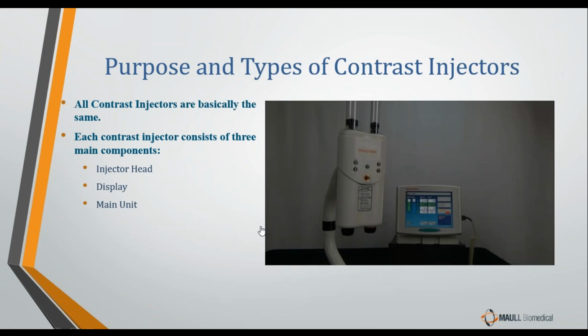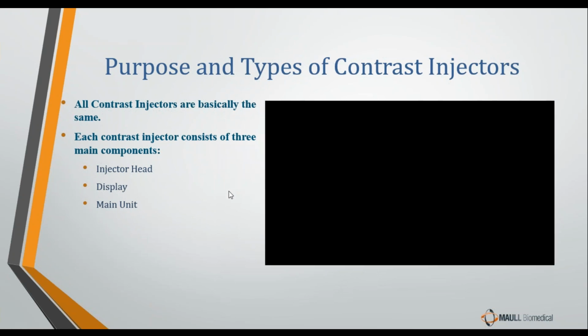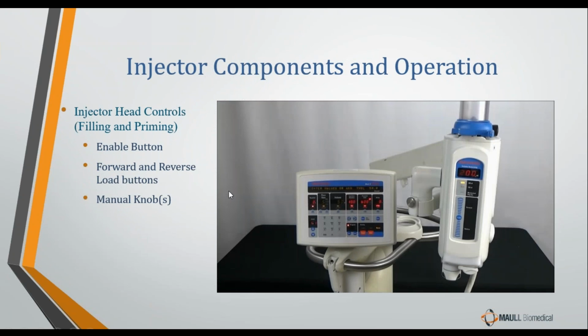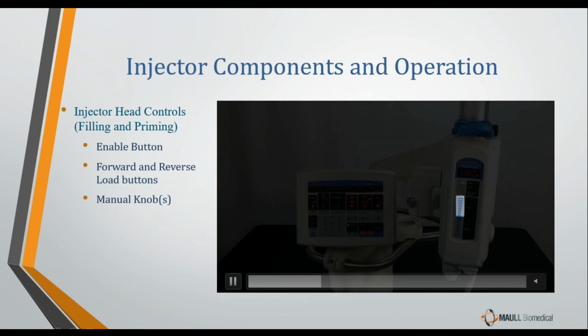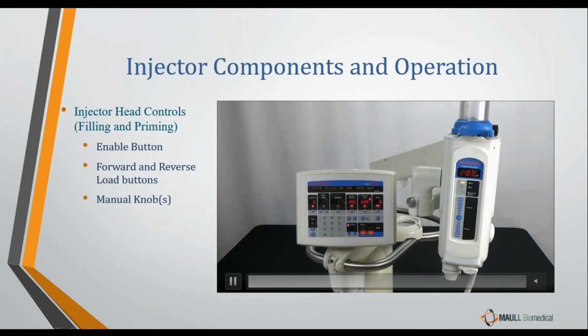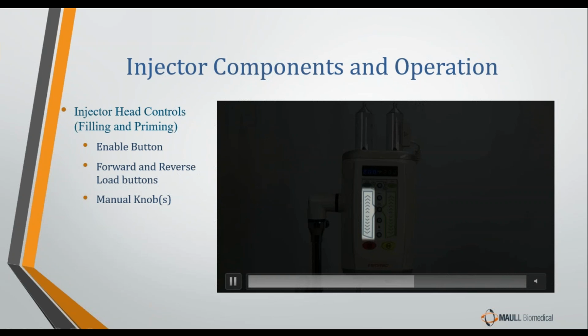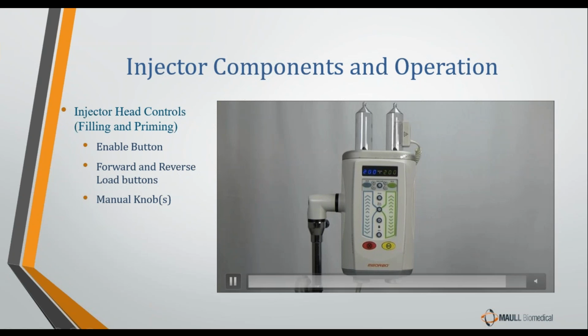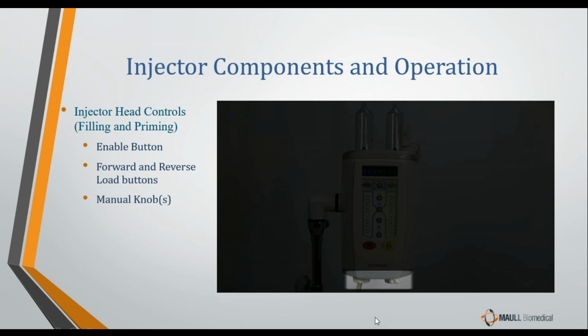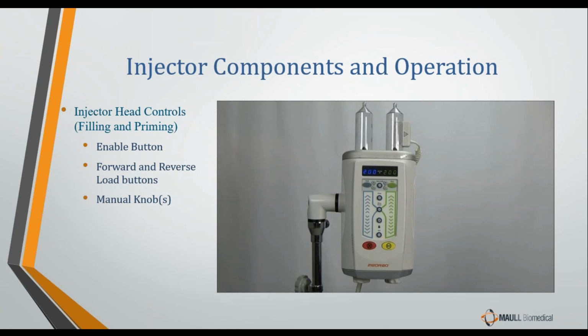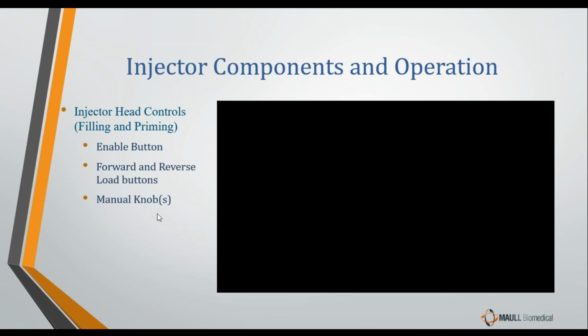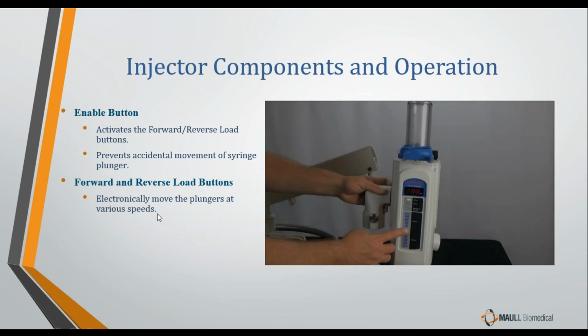So first off, let's go over the injector head. The injector head has certain buttons on it that allow it to be used. Those are the enable button, the forward and reverse load buttons that drive the plungers up and down, and the manual knobs down here at the bottom. There's your manual knobs down there. The purpose of these three controls on the injector head is to fill and prime the syringes with the fluid and then connect it to the patient.